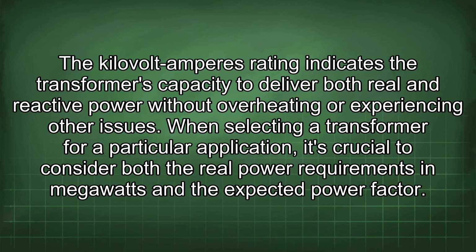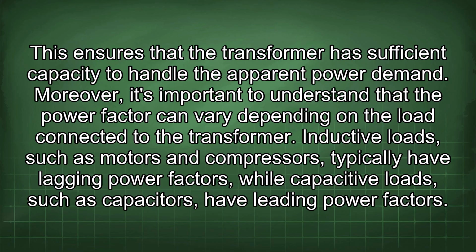issues. When selecting a transformer for a particular application, it's crucial to consider both the real power requirements in megawatts and the expected power factor. This ensures that the transformer has sufficient capacity to handle the apparent power demand. Moreover, it's important to understand that the power factor can vary depending on the load connected to the transformer.